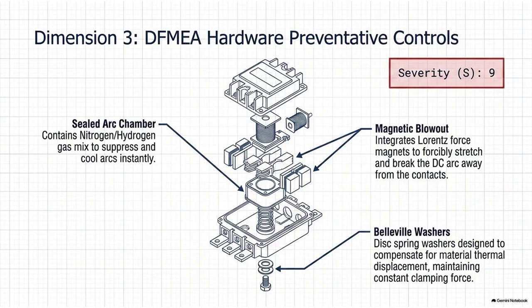And this entire chaotic, violent process happens in milliseconds. We are talking fractions of a single millisecond. The magnetic blowout architecture rips the arc apart so incredibly fast that the specialized silver tungsten alloys on the contacts literally do not have enough time to absorb the intense thermal energy and reach their melting point. The arc is blown out before the liquid phase can begin, preventing the metallurgical bond from ever forming. That is just an incredibly elegant piece of engineering, using the fundamental passive physics of electromagnetism to actively fight a volatile electrical problem. It's pure physics.